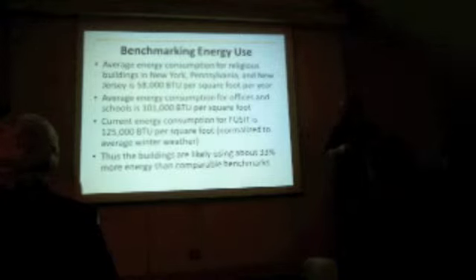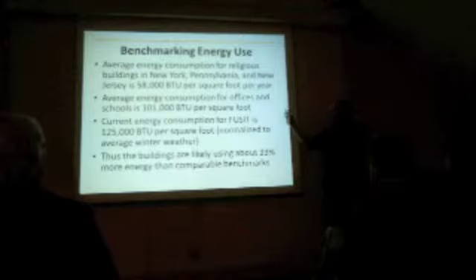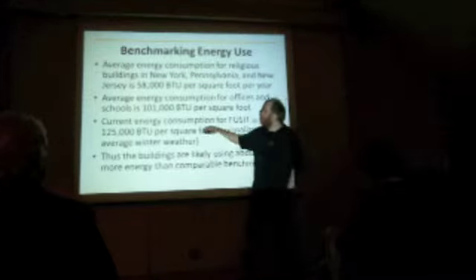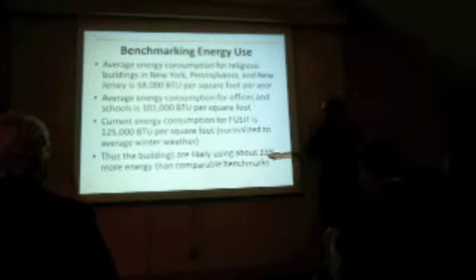So compared against those benchmarks, the 58,000 and the 101,000 BTU, if you take last year's energy bills for all of the buildings put together, which is this building and both floors of the annex, it works out to about 125,000 BTU per square foot. If you divide up the square footage between the two buildings, the office space and the annex should be closer to this 100. The sanctuary and some of the other spaces you would expect to be closer to the 58,000. So on average, we come out with a number that says these buildings are using about 33% more energy than the comparable buildings. So they're not bad. They're not far off from the average, but they're not already super efficient.